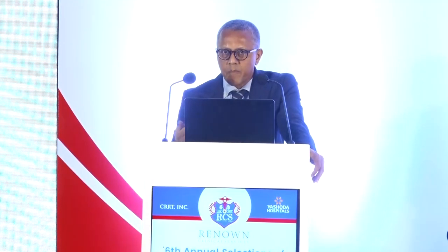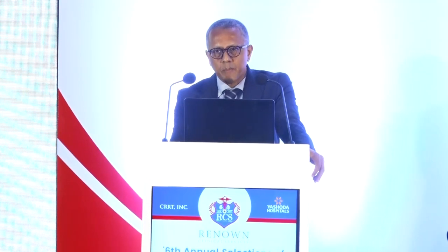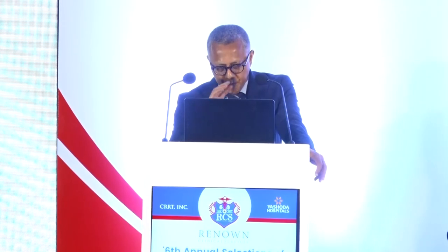The second pressure point monitored is between the blood pump and before the filter, measuring pre-filter pressure and reflecting everything happening from the filter downstream up to the return line. The third pressure is monitored in the de-aeration chamber — the return pressure — telling us anything downstream in the tubing up to the catheter and into the return. The fourth pressure is monitored in the effluent line, telling us the effluent pressure in the potential space where the fibers are suspended. From these four pressures, the machine calculates transmembrane pressure and filter pressure drop.